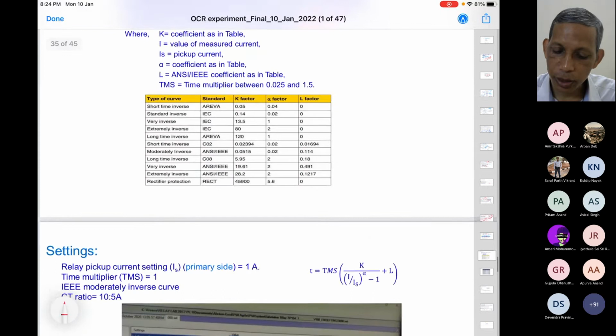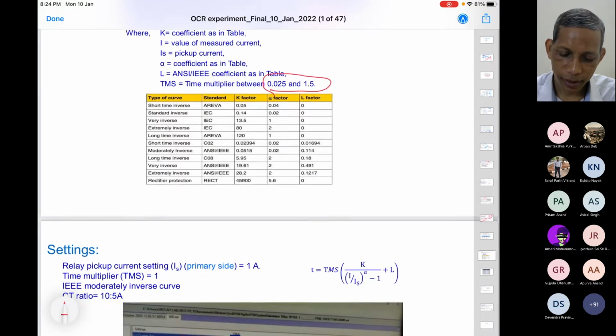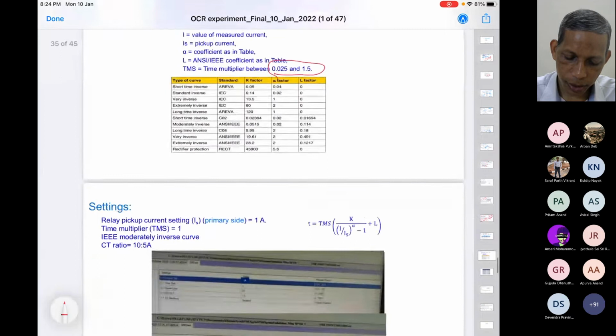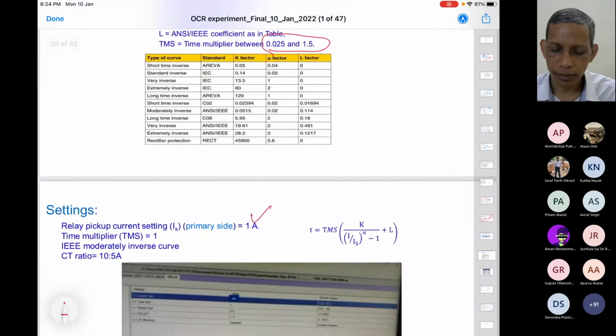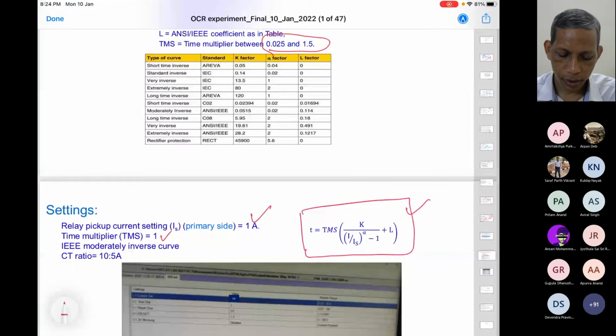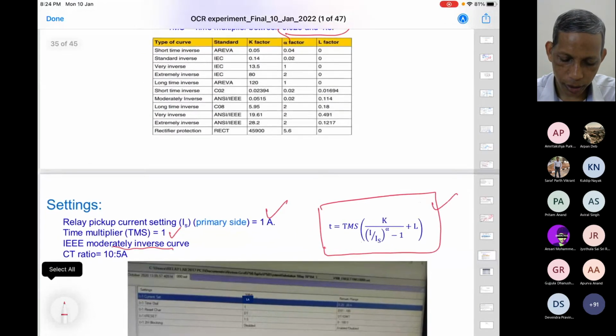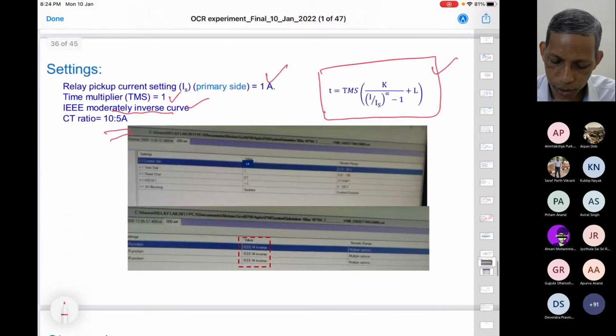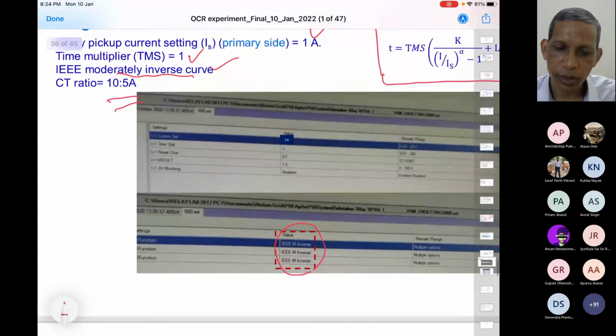These are the characteristics I was telling you about earlier. In this relay, the TMS variation range is 0.025 to 1.5, 0.025, very small. Agree? For our case, we took a 1 ampere pickup setting. In this example, we'll have more examples for different settings also. We have a time multiplier setting of 1 in this example, and the corresponding curve is the IEEE curve, moderately inverse. Okay? Moderately inverse. CT ratio is 10:5, as already mentioned.